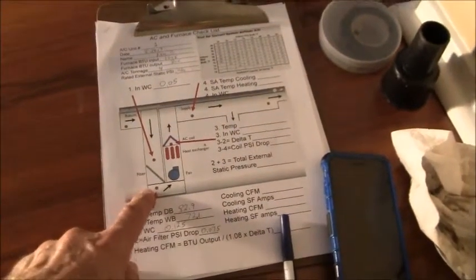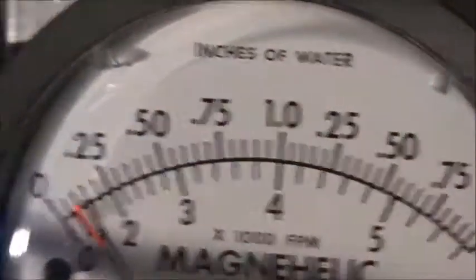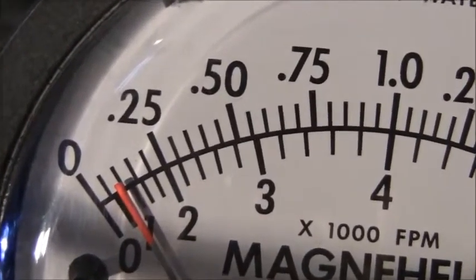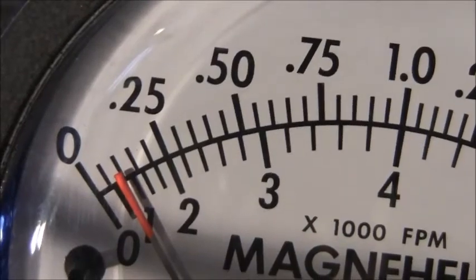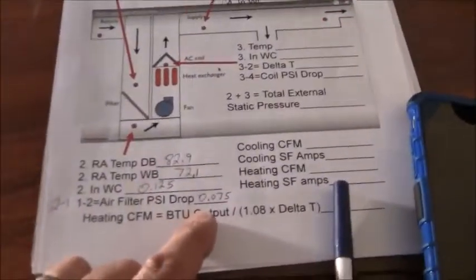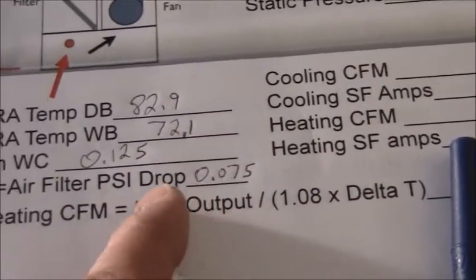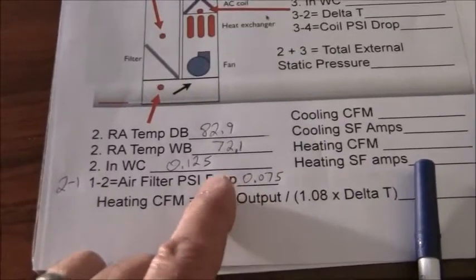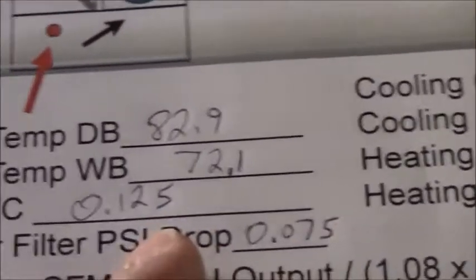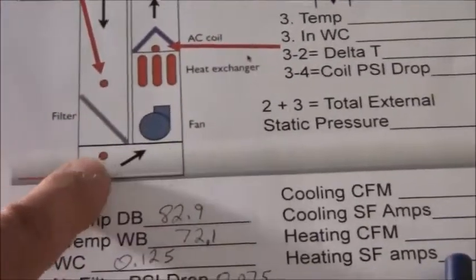The reason why that's a low probe, it's the lowest pressure in the system. It's just before the fan. Now, when I do that, this is what the reading is. It looks like it's 0.08. My mathematical reading on here is 0.075, pretty much the exact same number, okay? So this is just doing the math by taking each point individually, point 1, point 2, one at a time, and then doing the math on the calculator. And then here is the actual reading, just plugging the low and high ports directly in, confirming that information. Let's continue on with our analyses.